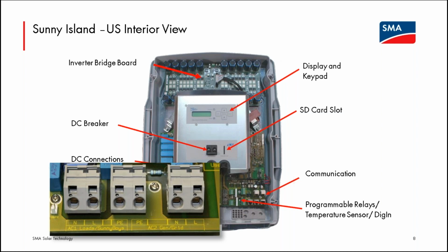There are two relays in each Sunny Island that can be programmed to do certain functions based on potentially state of charge, based on time, based on what charging cycle the batteries are going into. So they're very, very useful. And again, there's two relays per Sunny Island. So if a system was using 4 Sunny Islands, you have 8 potential programmable relays to utilize. It's very, very useful, particularly for off-grid systems.